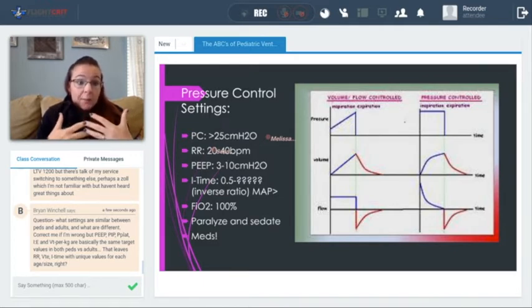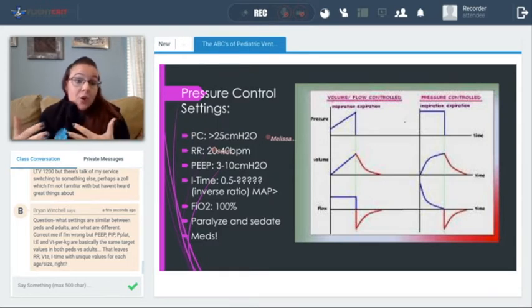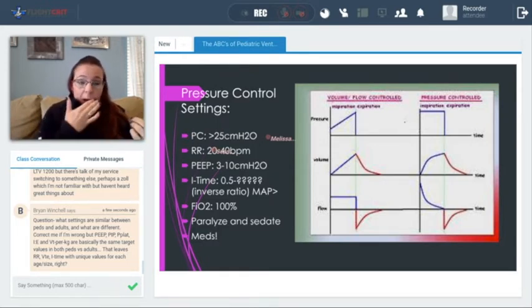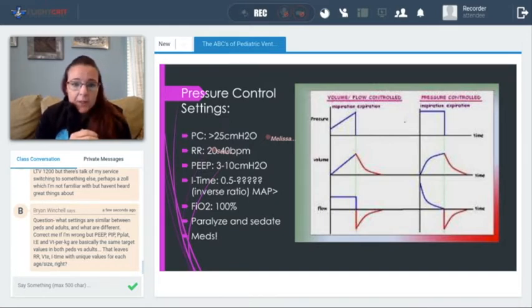So for me, on my vent, because it's not PEEP compensated, I would set my pressure control setting at 30 and my PEEP at 10, or my pressure control setting at 35 and my PEEP at 5. That is probably different for a lot of your vents out there. I can't remember with the 1200. I'm pretty sure a lot of those have an external PEEP valve, but I know that T1 is steps above a lot of our ventilators right now. So you guys are pretty lucky if you get to use that vent in your transport. I'm looking forward to having access to that ventilator pretty soon.